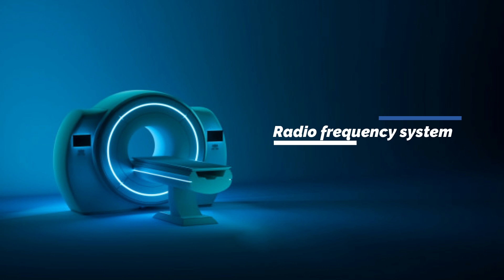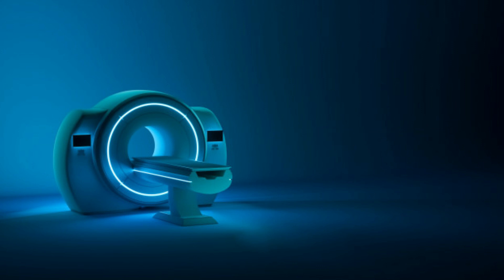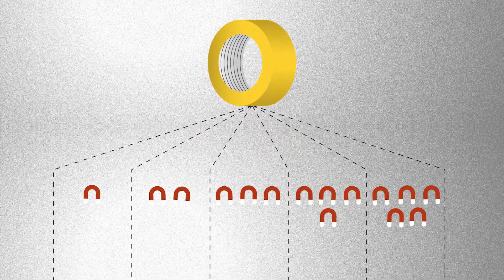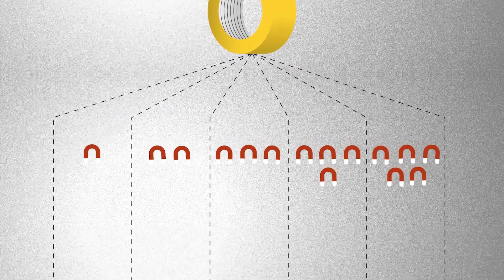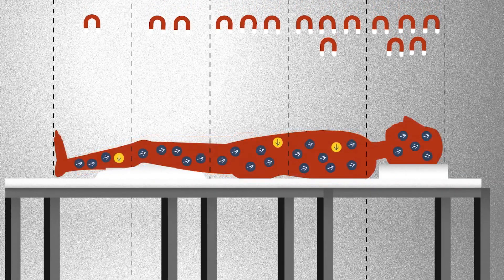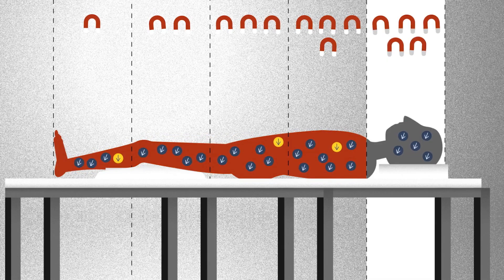The third component in MRI systems is the radio frequency system. The radio frequency, or RF, transmission system consists of an RF synthesizer, power amplifier, and transmitting coil.